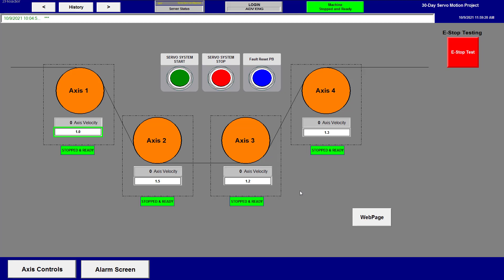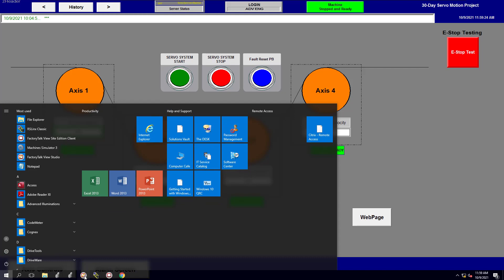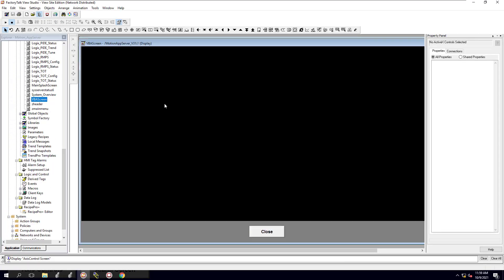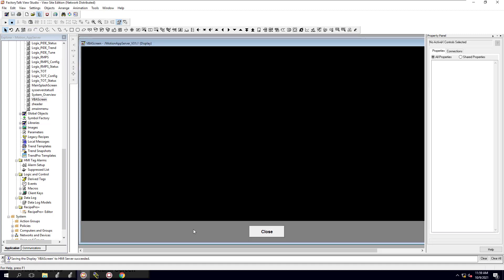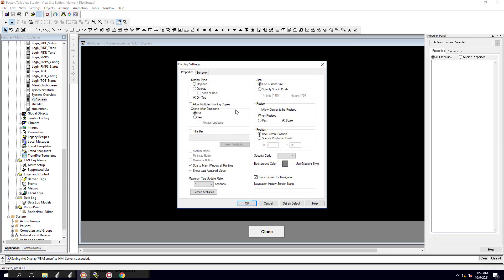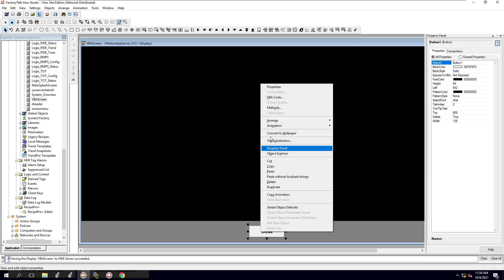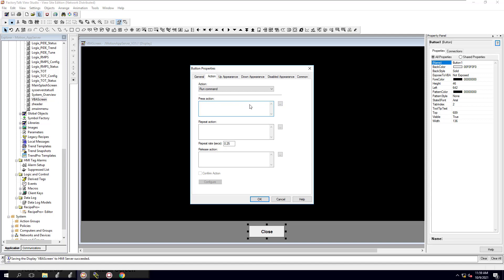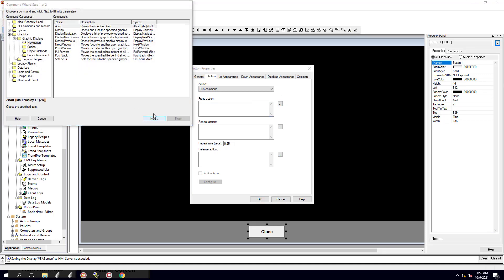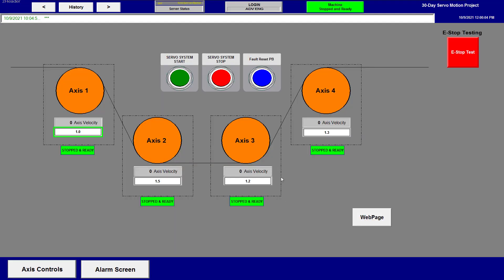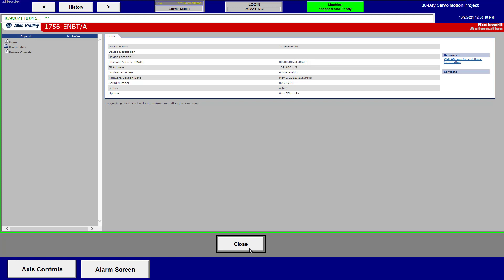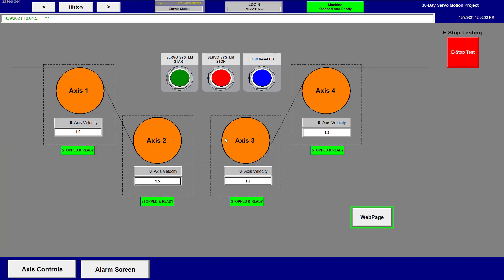You can have the abort done in many different ways — like if you want the screen to come up on top, just change the screen properties from Replace to On Top. And then for the abort, go in and change it from aborting a specific screen to Close Active Window. Now when you refresh and push the button, it overlays on top, and aborting just closes it. So you get a couple of quick tips: the screen doesn't disappear — it comes on top, gives you the information, and then closes. You're back to your normal settings.